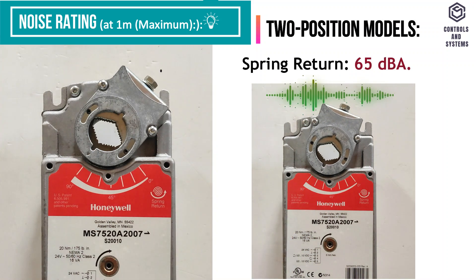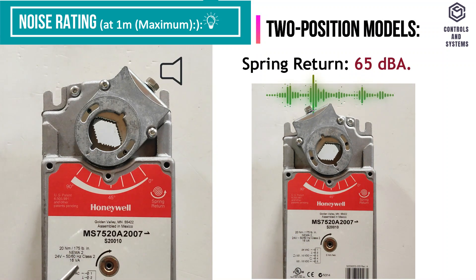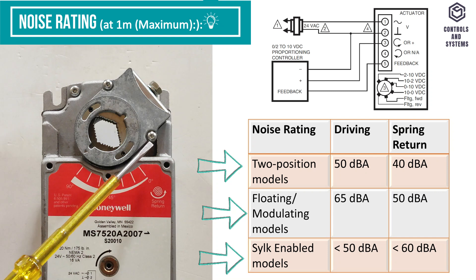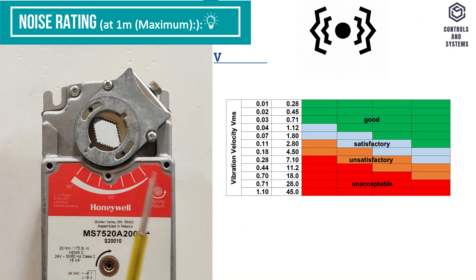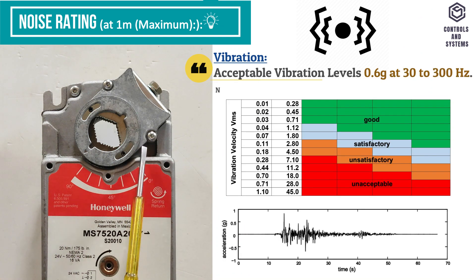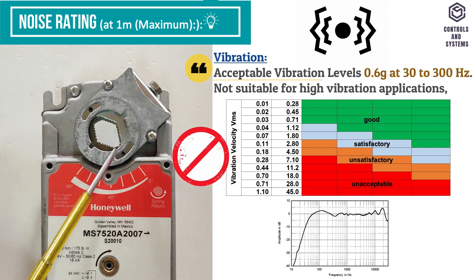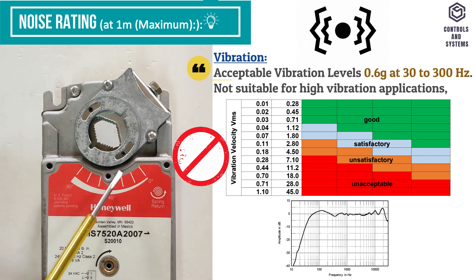In spring return is 65 decibels A. The table indicates the noise ratings for the floating, modulating, and Sylk Enabled models. Acceptable vibration levels are 0.6 g at 30 to 300 hertz; not suitable for high vibration applications.